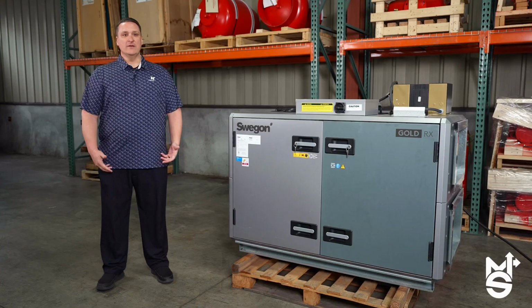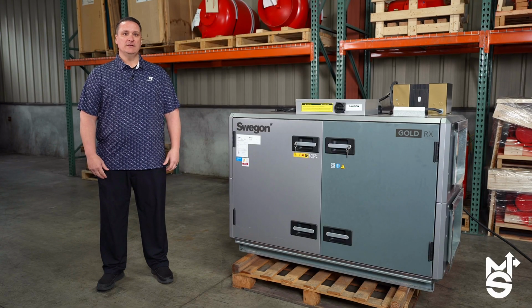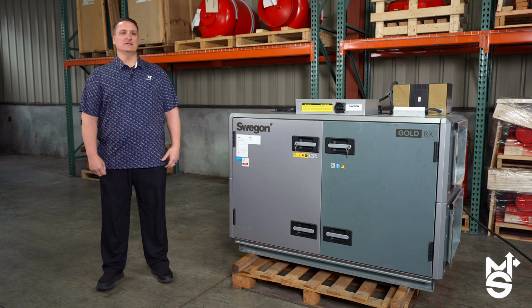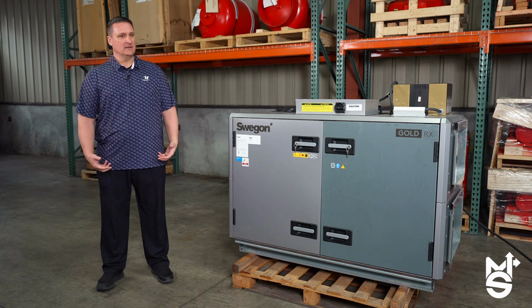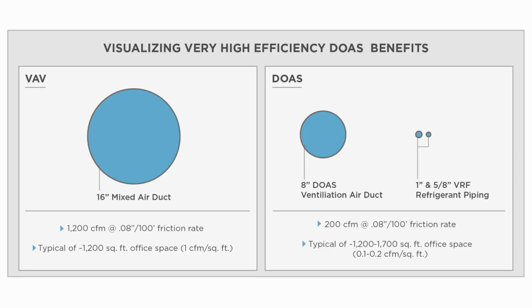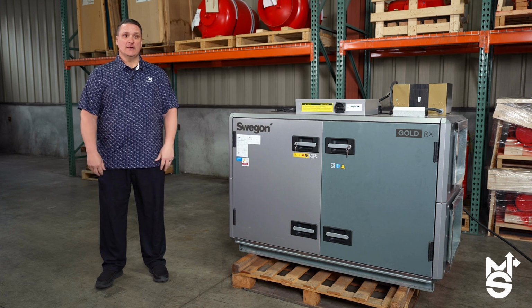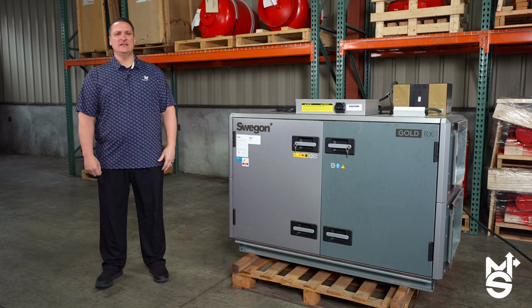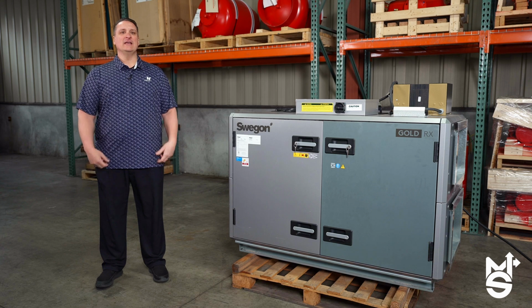A VHE DOAS system starts with right-sized equipment to deliver ventilation air, heating, and cooling to the building. The ventilation efficiency is achieved by only delivering the amount of dedicated outside air necessary to meet the occupant ventilation requirements by code. These smaller airflow amounts result in smaller building ductwork, smaller air distribution equipment, and in conjunction with the very high efficiency energy recovery ventilator of the Swegon Gold RX ERV yields tremendous savings to the life cycle cost of the building. This calculated amount of dedicated ventilation air is delivered to each zone individually at what we define as neutral air temperature, typically in the lower 60-degree range.